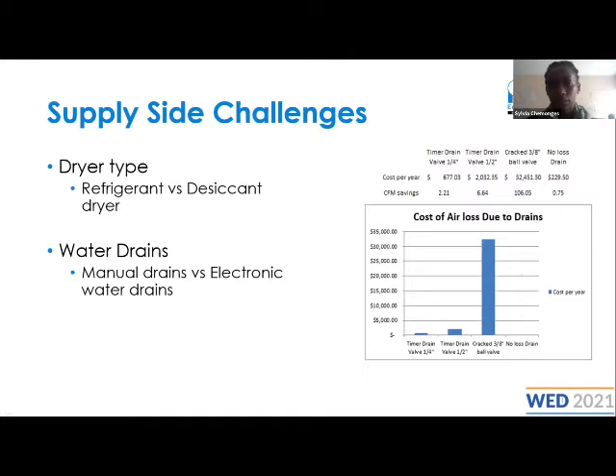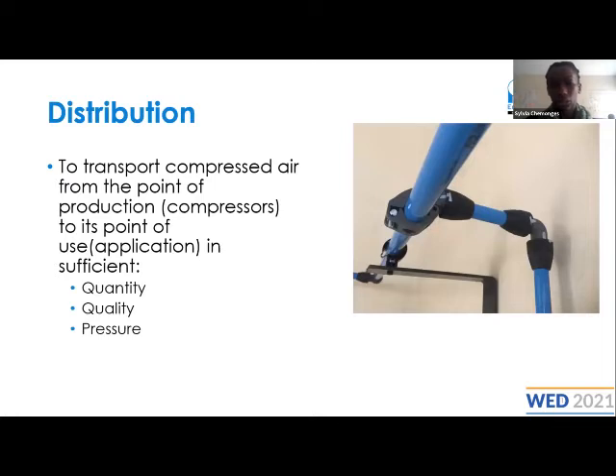Then from there, we look at the distribution side. From the supply side, we go through to the distribution side. The distribution side is where we transport compressed air from the supply side to where it's needed. It encompasses the piping system that you use. A key component in designing a good distribution system is the quality of compressed air. You need to look at the quality of the compressed air supply, the pressure, the quantity, and the flow rate. Those three components will help you select a good distribution system.